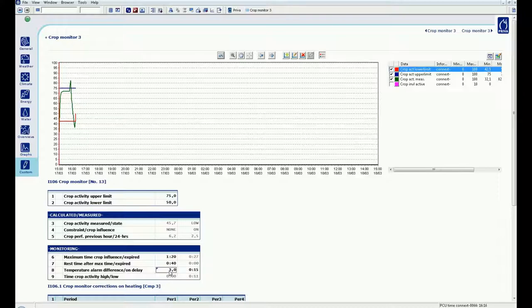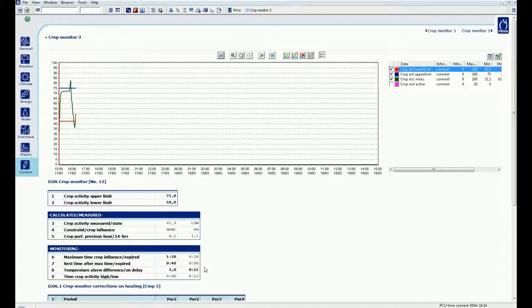Then there is a control on the measurement. You will set a limit for the difference in temperature between the plant temperature and glasshouse temperature. In my case, it is set to 3 degrees difference and with a delay of 15 minutes. This is the difference in temperature restriction which was mentioned earlier in constraint.